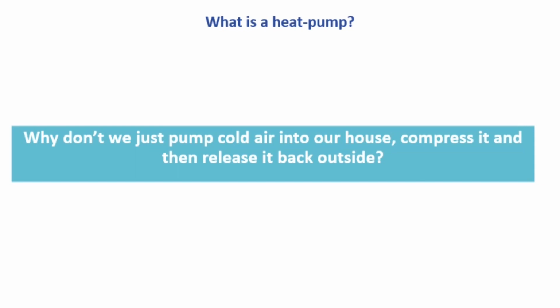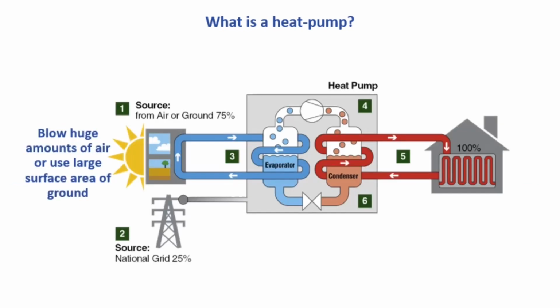So instead, what we have is a heat pump, and rather than pumping air directly into a house and compressing it, what we use is an intermediary fluid called a refrigerant that does the heat exchange process for us and is able to carry heat with a much greater density, if you will, in comparison to air. So this diagram shows the layout, and if you look at number 1 over the top left, you've got the source. You get air source or ground source heat pumps.